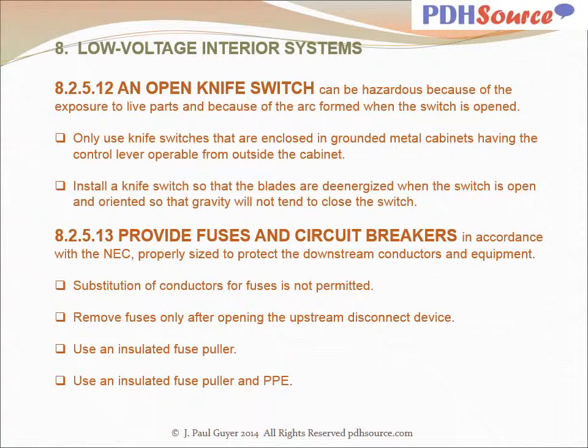An open knife switch can be hazardous because of the exposure to live parts and because of the arc formed when the switch is opened. Only use knife switches that are enclosed in grounded metal cabinets, having the control lever operable from outside the cabinet. Install a knife switch so that the blades are de-energized when the switch is open and oriented so that gravity will not tend to close the switch.